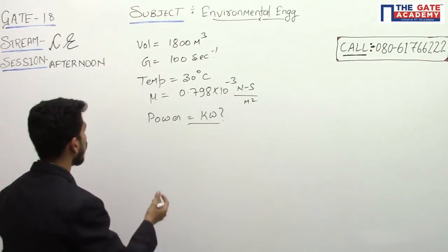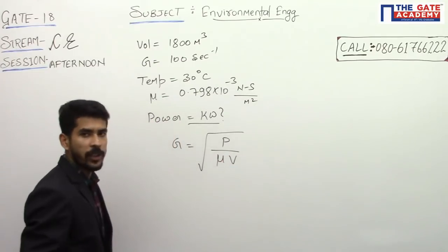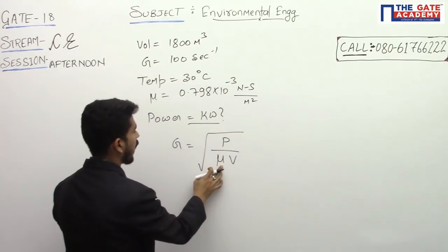For a flocculation tank we know that G is equal to under root of P divided by mu into V. P is the power, mu is the dynamic viscosity of water, and V is the volume.